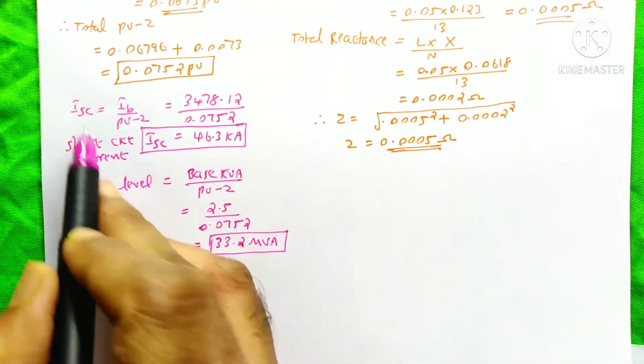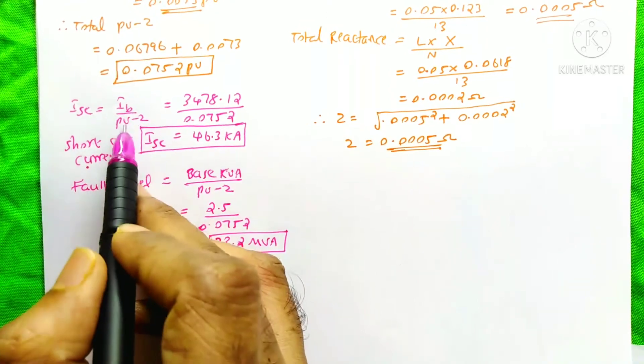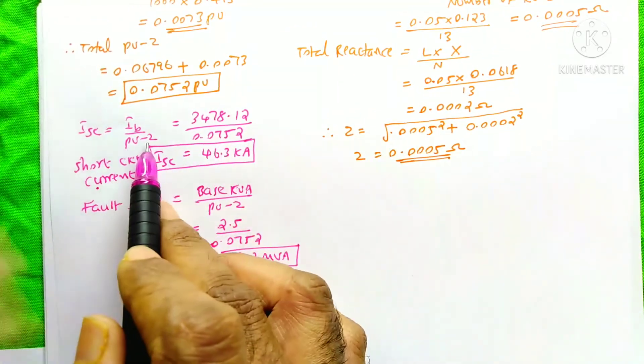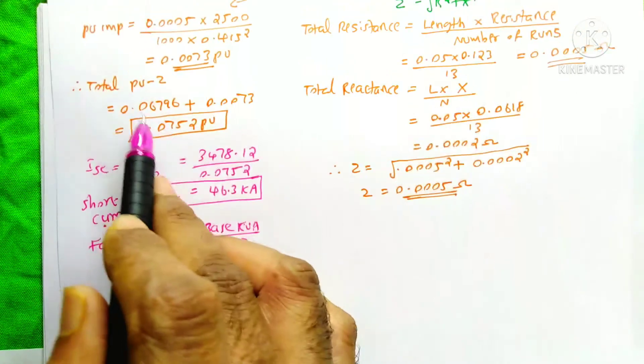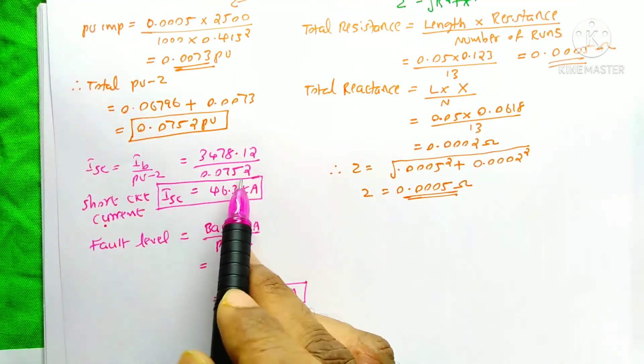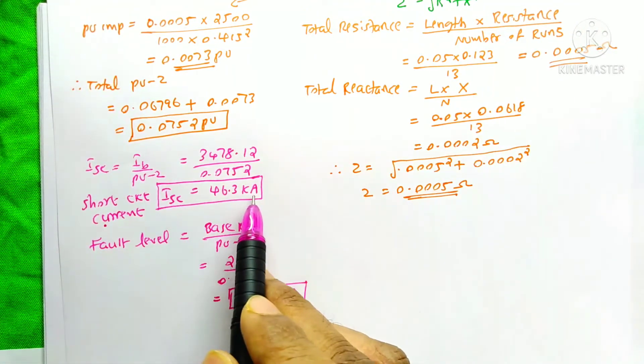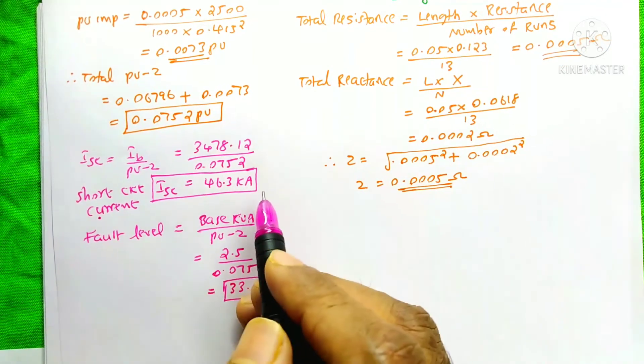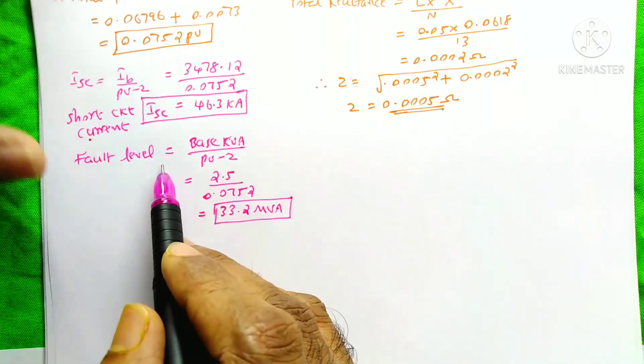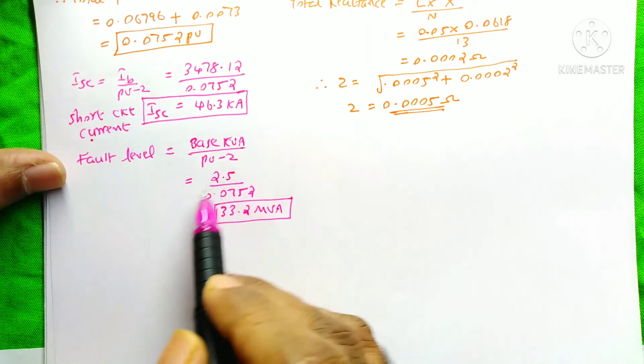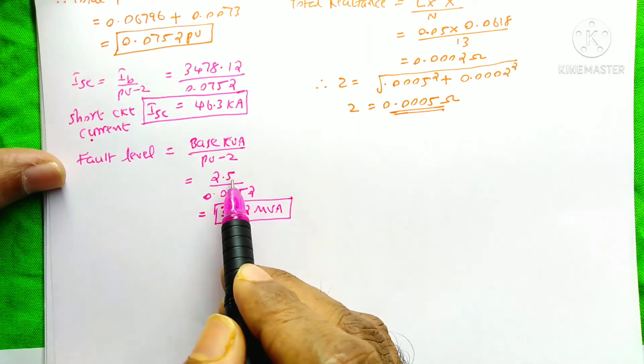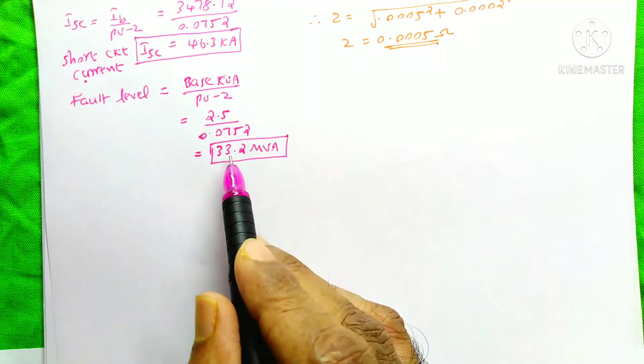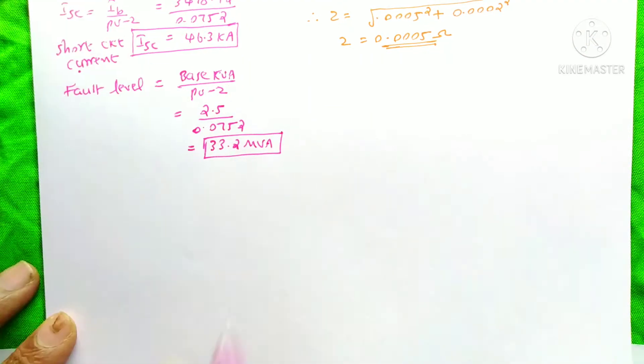Now calculating the short circuit current at the LV panel: ISC equals IB divided by per unit impedance. IB has no change, divided by the total per unit impedance of 0.0752. The answer is 46.3 kilo Amps short circuit current at the LV panel. The fault level is base kVA divided by per unit impedance: 2.5 MVA divided by 0.0752, giving 33.2 MVA.